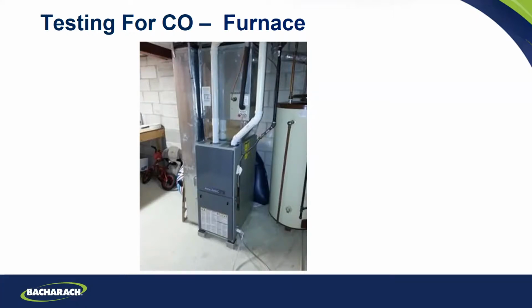You guys that are on boiler work, you want to check the same things as well as mechanical situations. Maybe you check your combustion going up, but then you want to check your combustion going down because you may have slop in your linkage. If those don't match going up or down, it's a mechanical problem. I was called up into Canada where a company put in 2 package boilers, both from the same quality manufacturer, and one had very low CO, under 100, and the other one had very high CO, over 8,000. They just knew it was very high. Their unit went to 4,000 ppm and just loaded up, and so they blamed it on our unit.